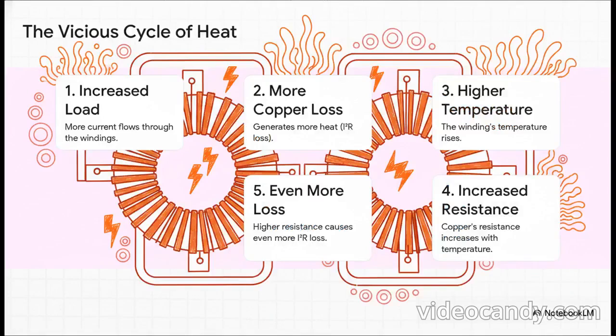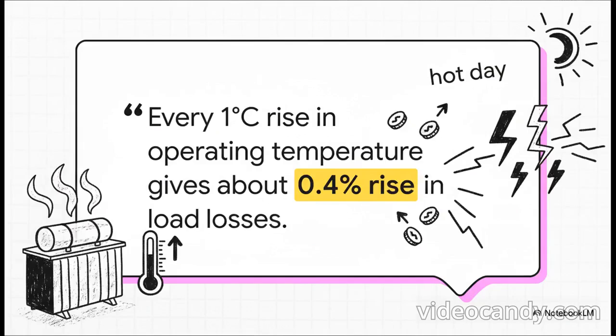But it actually gets worse. Heat creates a really nasty feedback loop. More load means more current, which means more copper loss, which generates more heat. A hotter transformer means its copper wires actually have more electrical resistance, and more resistance means even more heat from I squared R loss. It's a vicious cycle that just keeps spiraling, making the transformer less and less efficient the harder and hotter it runs. And this isn't a small effect.